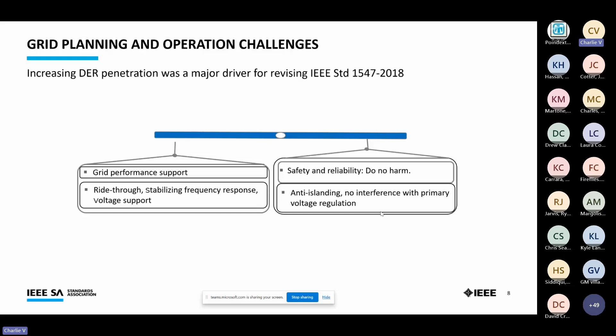With increased penetration of renewables, there's an increasing need for capabilities that provide grid performance support, and your proposed updated rule catches the big ones like ride through. What's great is this is a real win-win: newer technologies can deliver these many times as an inherent product capability, they just need to be specified and implemented, often at minimal cost with great returns to all sides. This has had great success lifting renewable hosting capacity in markets like California and Hawaii, early adopters even before 1547-2018 was approved, with their own tariff rules—Hawaii Rule 14 and California Rule 21—calling out specific smart grid capabilities that kept them ahead of severe hosting capacity constraints.